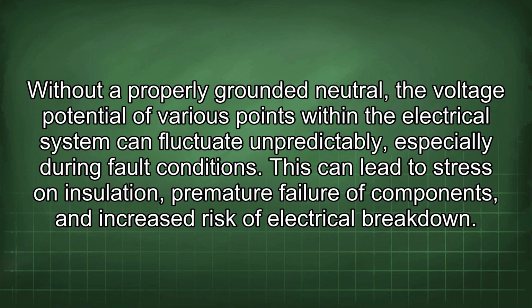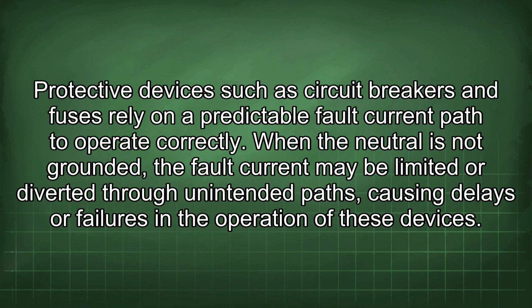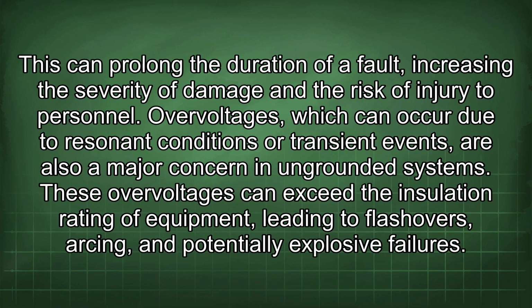This can lead to stress on insulation, premature failure of components, and increased risk of electrical breakdown. Protective devices such as circuit breakers and fuses rely on a predictable fault current path to operate correctly. When the neutral is not grounded, the fault current may be limited or diverted through unintended paths, causing delays or failures in the operation of these devices. This can prolong the duration of a fault, increasing the severity of damage and the risk of injury to personnel.